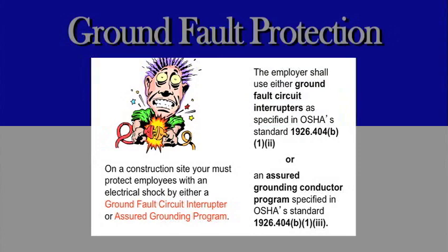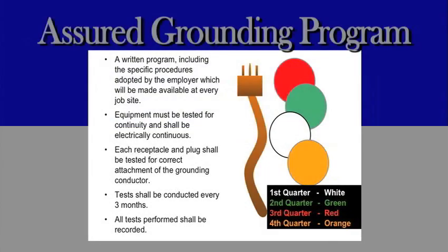The employer shall use either ground fault circuit interrupters as specified in OSHA's standard 1926.404(b)(1)(ii), or an assured grounding conductor program specified in OSHA's standard 1926.404(b)(1)(iii). On a construction site, you must protect employees from electrical shock by either a ground fault circuit interrupter or an assured grounding program. Assured grounding program: a written program including the specific procedures adopted by the employer, which will be made available at every job site.